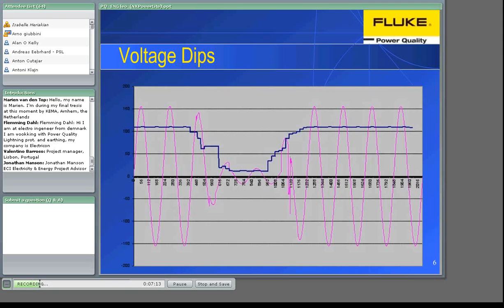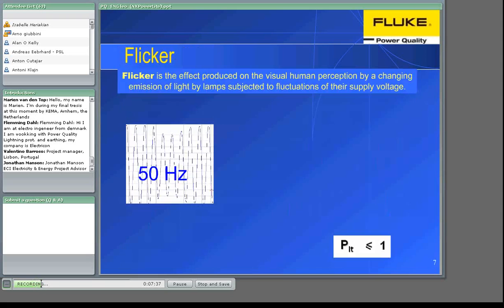Now, a voltage dip can be graphically represented, as you see on your screen, in two ways: as a sine wave or as an RMS value, which is actually more usual. Both provide the same information: start, stop, duration, magnitude. The advantage of the RMS value is the reduced size, which can save memory and accelerate data transfer in case of a remote communication.